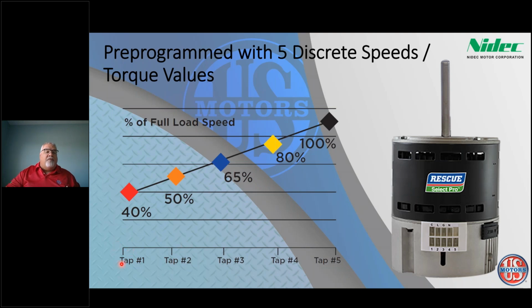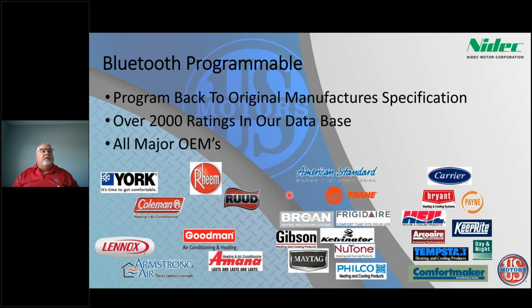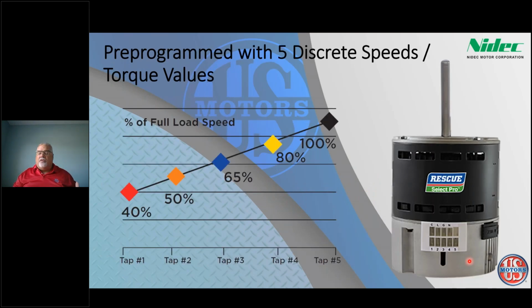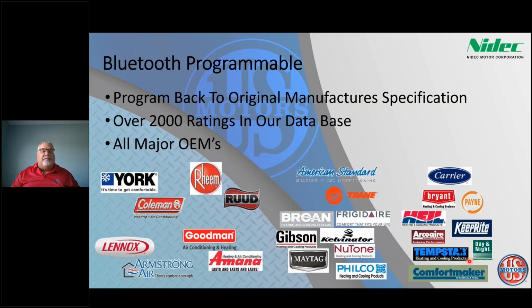Again, tap 1 is 40% of full speed, tap 5 is 100%. Exactly the same. The difference is it's Bluetooth programmable, meaning we've added into the bottom module here a Bluetooth dongle, so you can actually Bluetooth direct to this motor and program it back to the original OEM specifications.